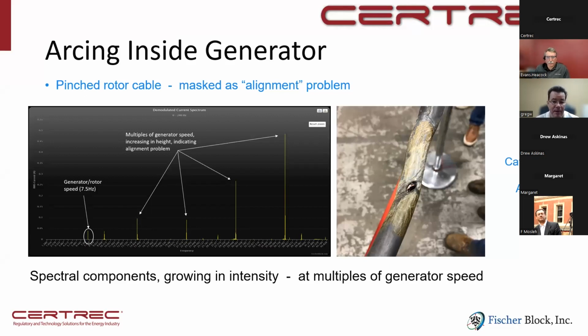And this is an interesting use case whereby in the frequency spectrum there, we saw and observed distortions at multiples of motor speed. And that's typically a classic signature of an imbalance in the shaft. And so that's what we alerted on at that time. This was a few years ago. When they went in and did the inspection, they actually found a pinched rotor cable that was arcing at a frequency associated with generator speed. And that now has become a warning sign. If we see this type of signature, it may be an imbalance, but it may be some type of pinched cable.